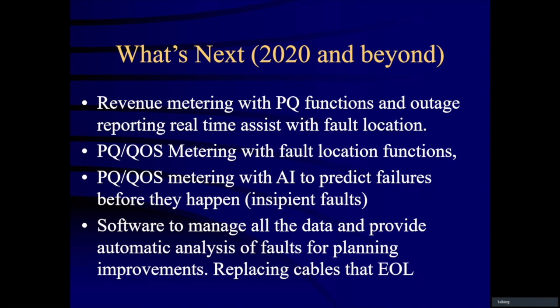The power quality metering, not so much, but quality of supply metering can now give the utility very quickly fault location identification. If they start integrating more artificial intelligence, it will predict failures before they happen. That's because of this incipient fault issue. The software to manage all this data and provide automatic analysis of faults for planning improvements.